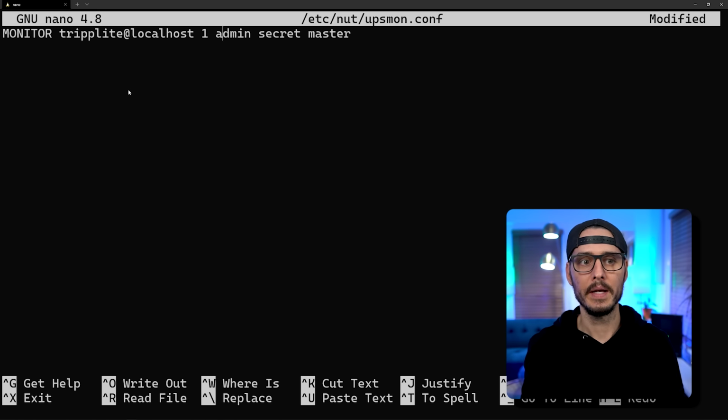How many UPSs are connected, and then some credentials, and then whether or not it's a master or a slave. So the way I set mine up is I treat mine as a master if it's physically connected to the UPS. So this one is physically connected to the UPS, so I'm going to say he's master. And for me, it's easier, rather than using master and slave, to use client or server terminology. Now, I know it's not a one-to-one with the way that they designed it, but it's easier for me in my head to think this is going to be my server and other connected devices will be the clients.